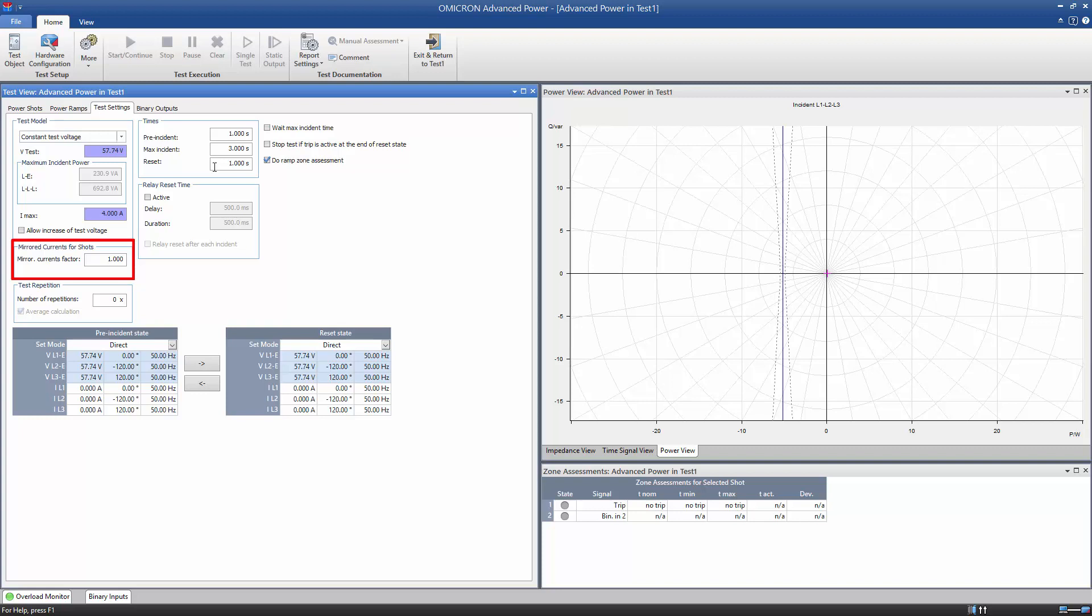This feature works for shot tests and can be used when testing a particular function of a multifunctional relay with an integrated differential protection feature. In this case, the Mirrored Currents setting ensures that this differential protection feature does not cause tripping.